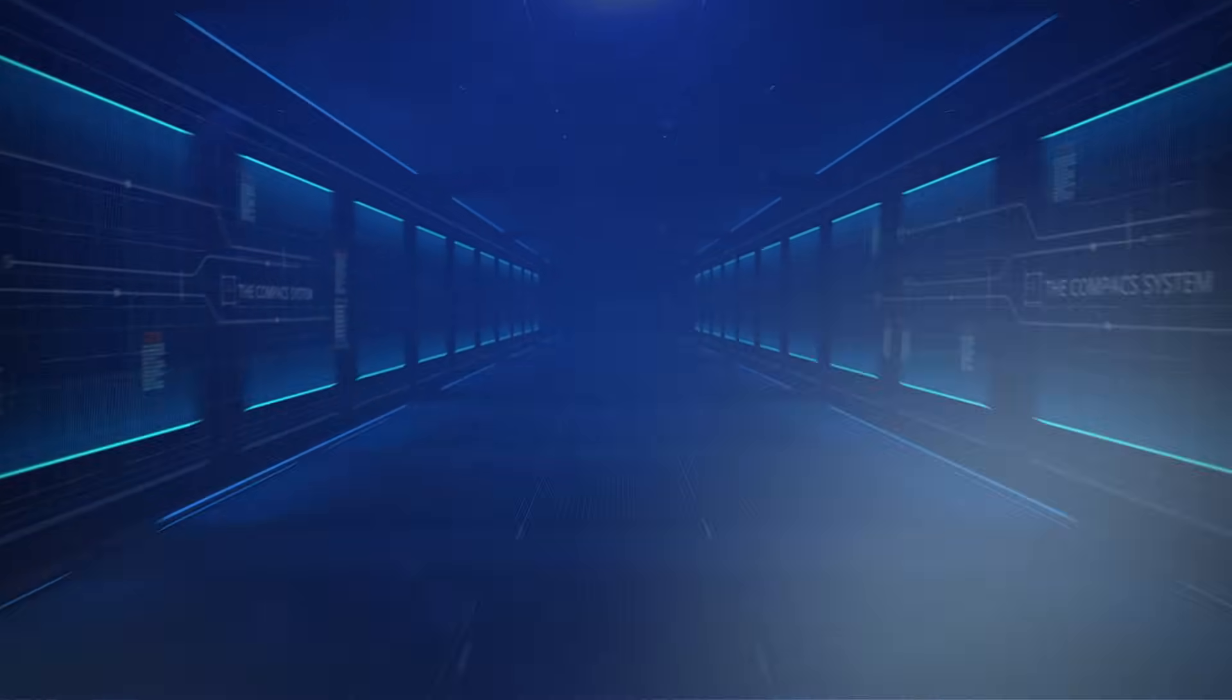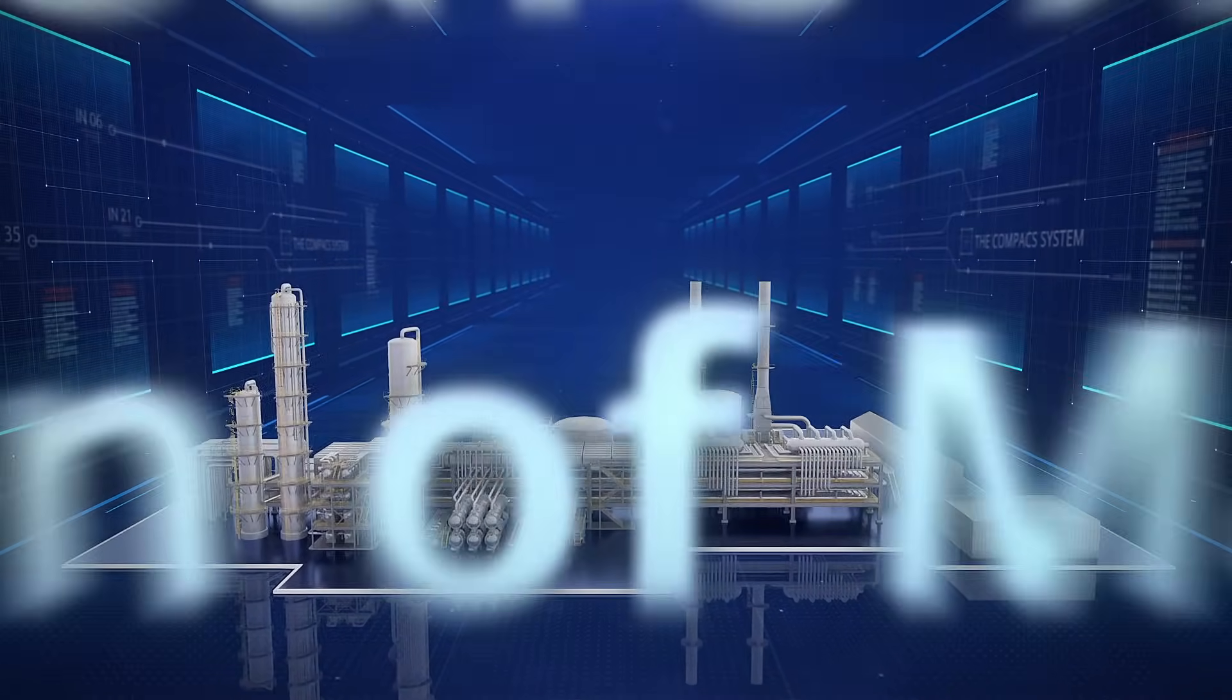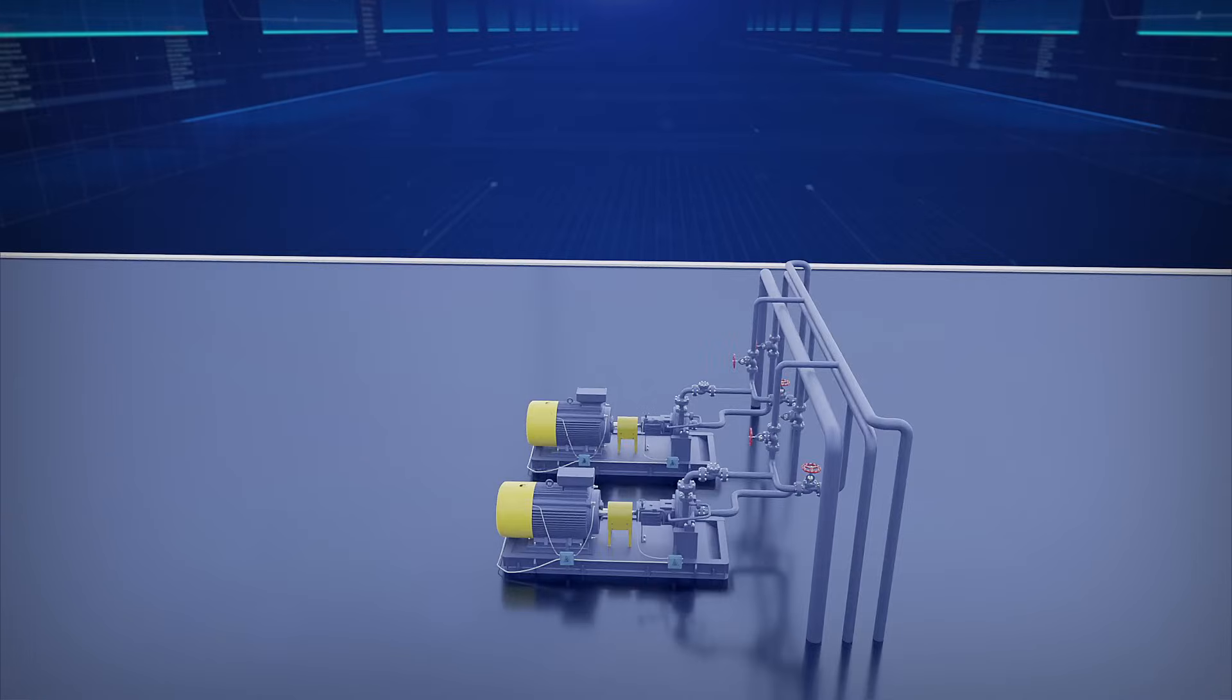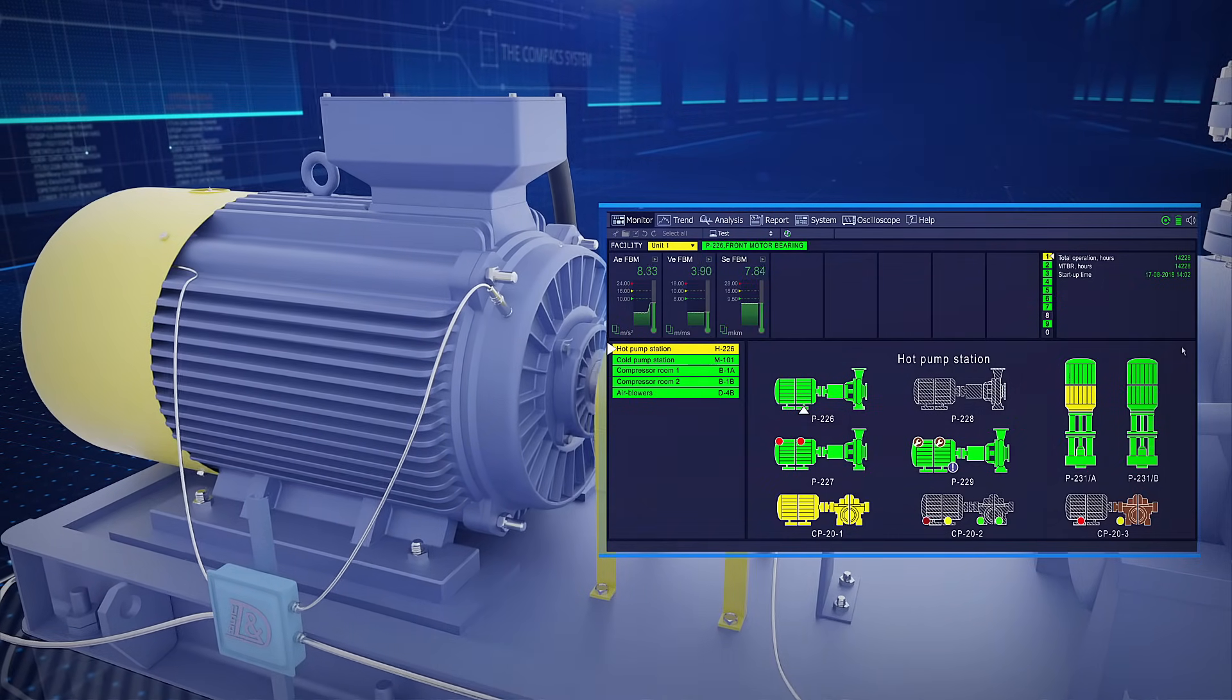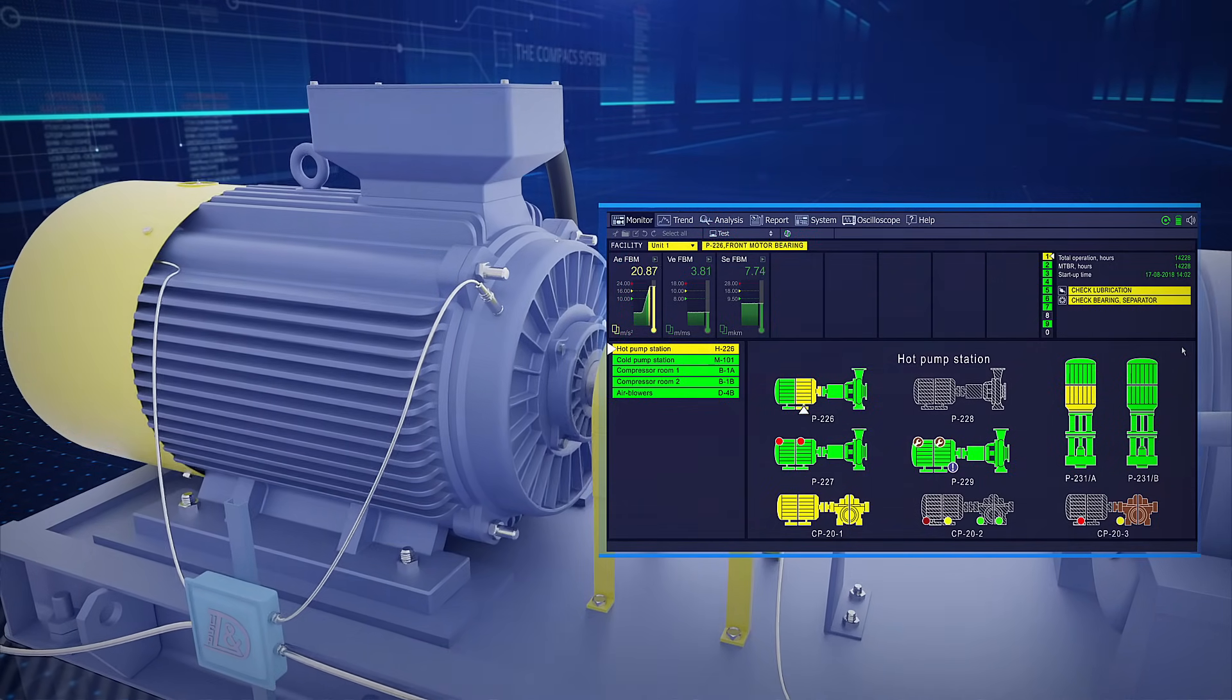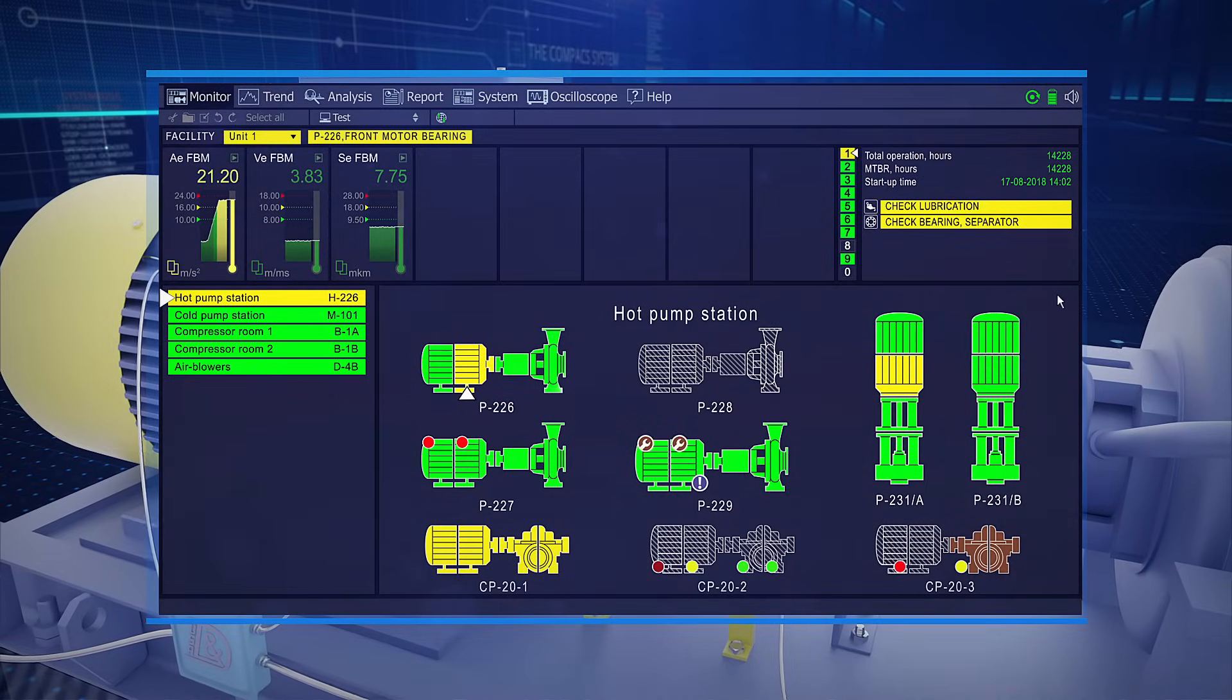Let's consider a case study of pump operation under the control of the compact system at the crude distillation unit. In February 2021, the vibration parameter indicative of lubrication presence on the front bearing of the induction motor slowly increased from 10 to 20 meters per second squared. The machine's health got worse, and the artificial intelligence of the compact system diagnosed lubrication problems in the front bearing and alerted the operators.